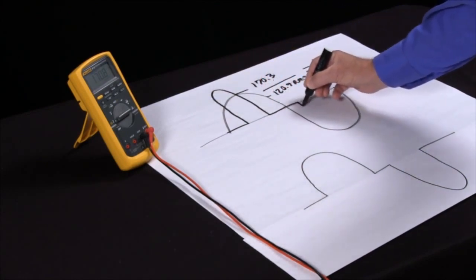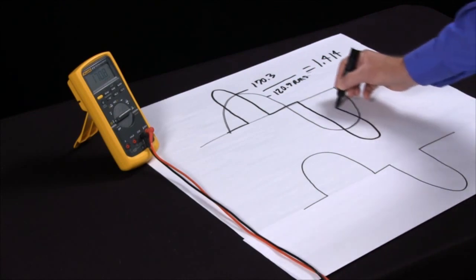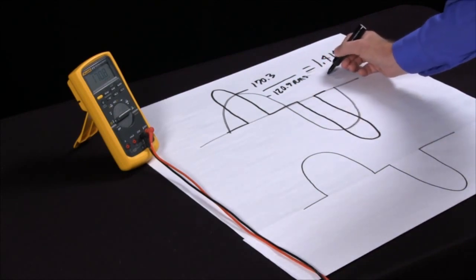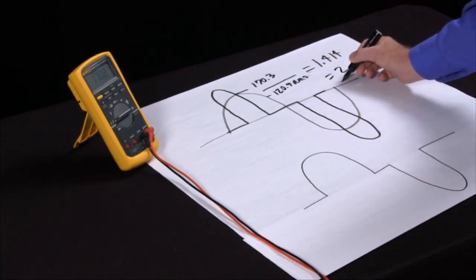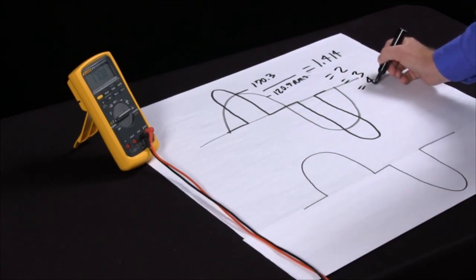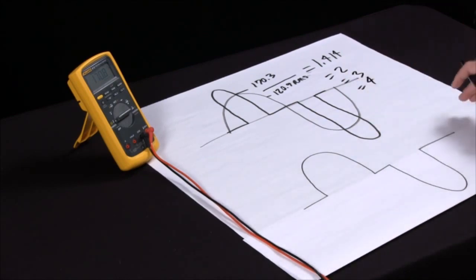So when I look at this ratio, I will start to see a ratio that will be equal to two, equal to three, maybe equal to four. This will be an indication that the higher the number is, the more harmonic distortion I have on the signal.